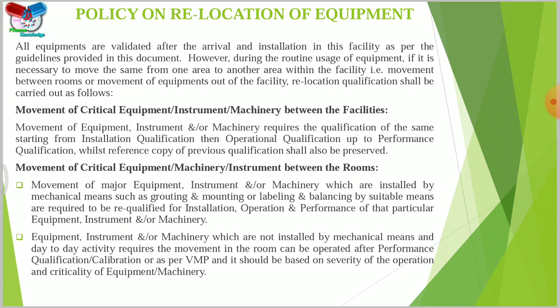And I think I covered all the phases. One change I missed: if you are purchasing older equipment from a different vendor, then there is a need for qualification of all these stages, because you have to verify the specification and the user requirement specification as per your requirement, whether the equipment is suitable for use, whether it is working properly, and whether the components are available. IQ, OQ, and PQ should also be performed. But you have to define in your VMP the approaches and the risk; it is a risk-based approach. It may vary depending upon the instrument and equipment. These are the main principles which I want to discuss with all.